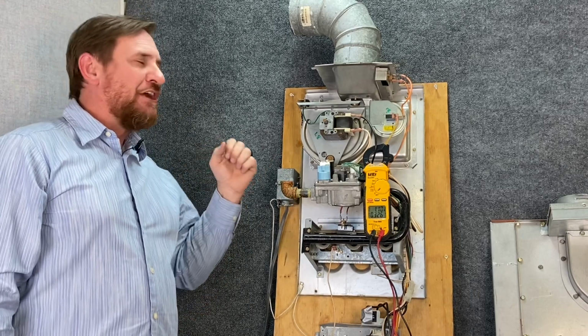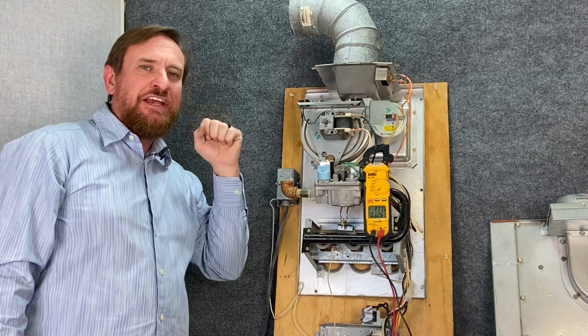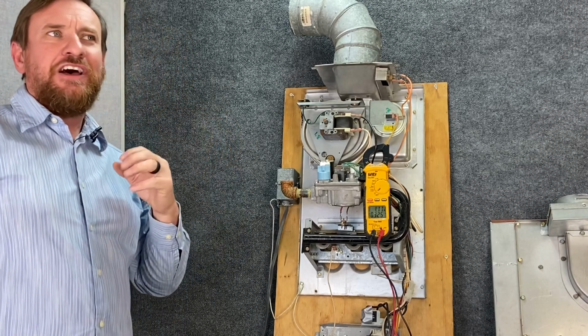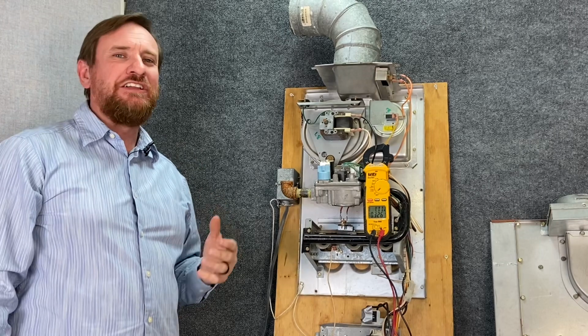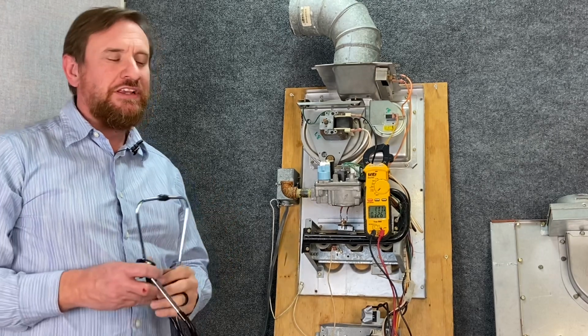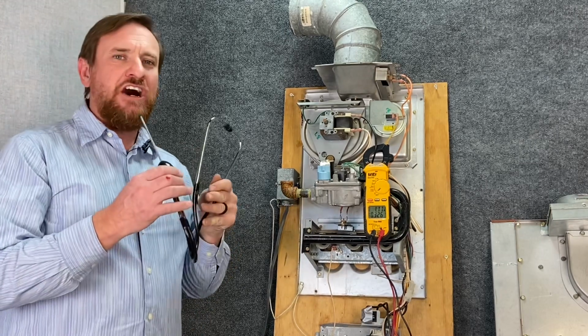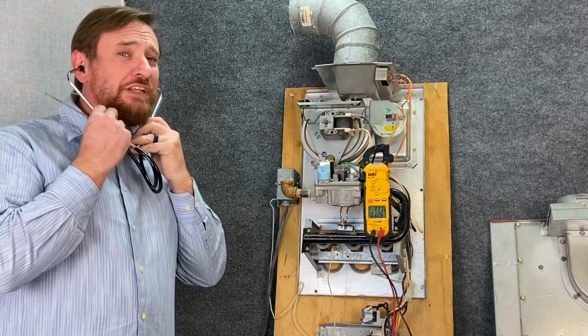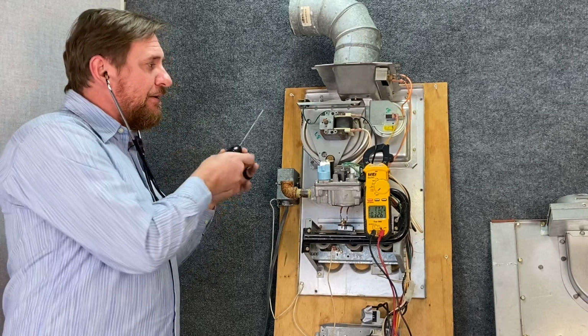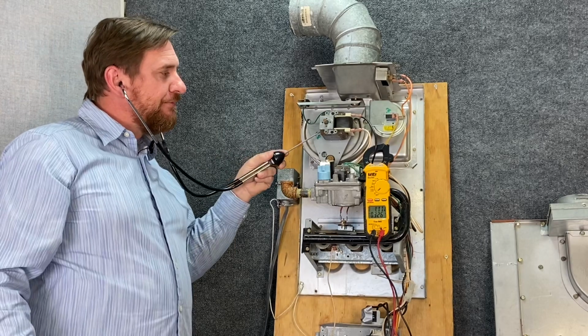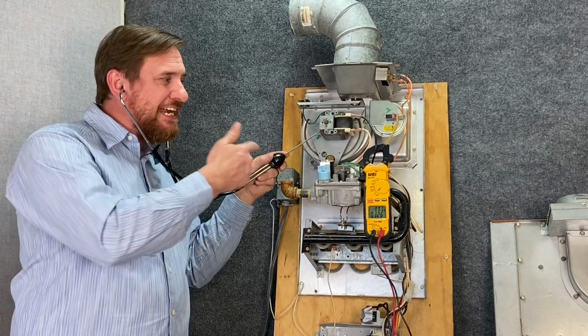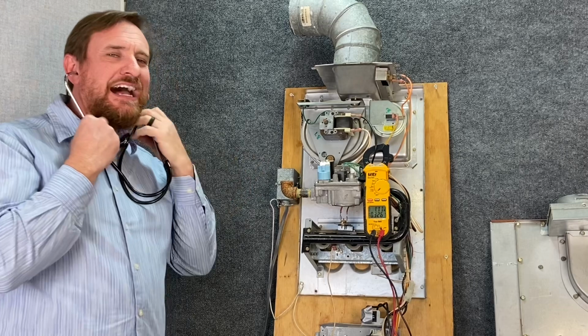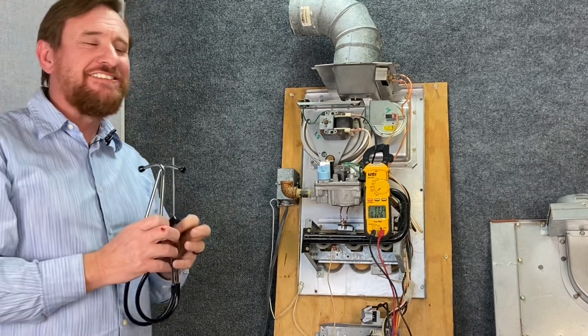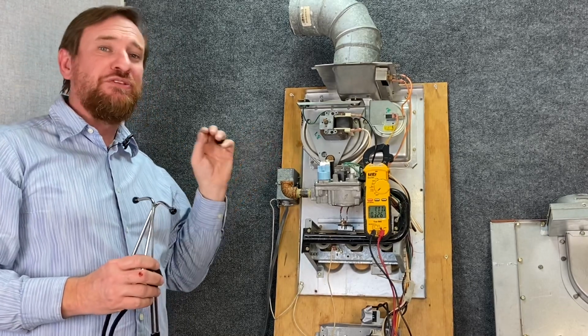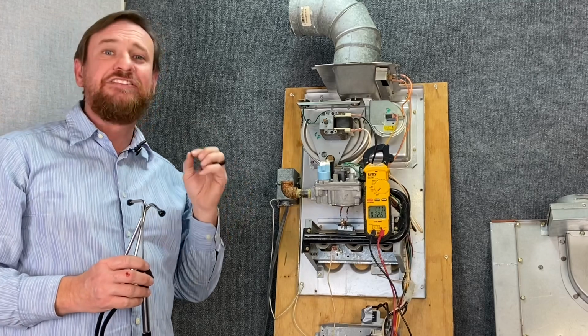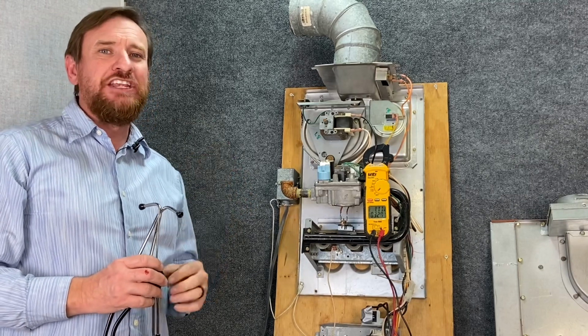But when I had a customer come up to me while I was listening to the bearings with a screwdriver to my ear, they thought, what the heck is wrong with this guy? And I tried to explain, but it was just really awkward. So now I've learned that you can buy these automotive stethoscopes that work really, really well. Put it in your ear, put it up against the motor, and you can literally hear the bearings turning inside. I can't describe what a good bearing sounds like. Once you hear enough motors and you hear one that's bad, you will know, wow, that is significantly different. We have an issue going on.